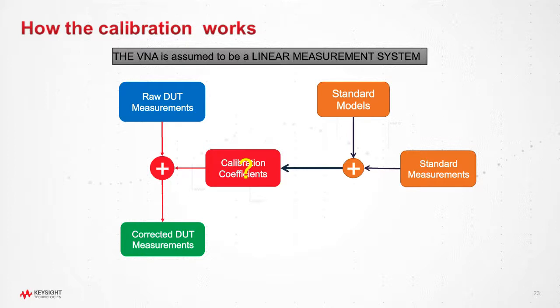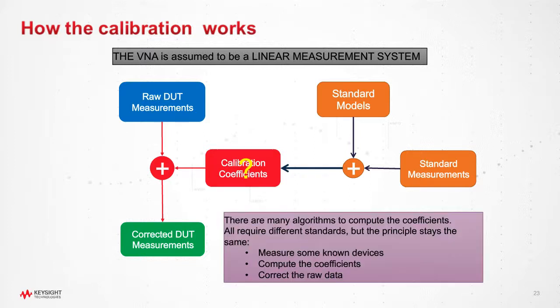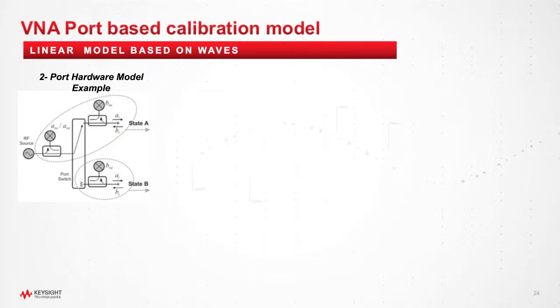This is exactly the same as when you want to calibrate a balance in our grocery store. There are many algorithms to compute the calibration, but the principle stays the same. Measure some known device, compute the error coefficients, and correct the raw data. Now let's come very briefly to our two-port VNA model to see what it is. So this is the VNA, a two-port VNA. When the source is connected to port 1, since you have two outputs, A and B, and you have two inputs, BM and BAM, this is linear. You will have 4 coefficients.